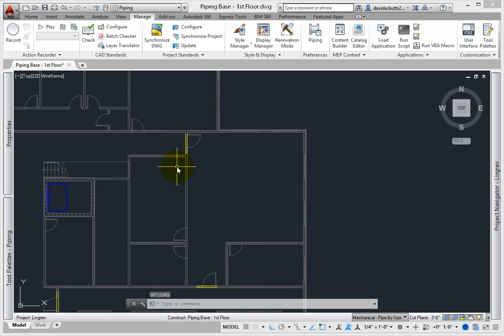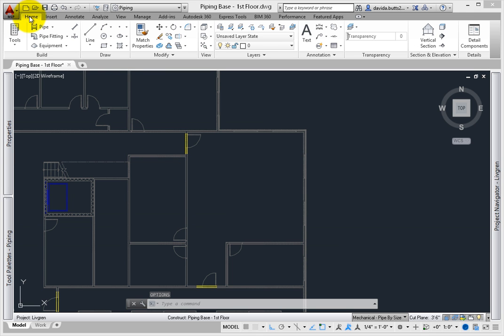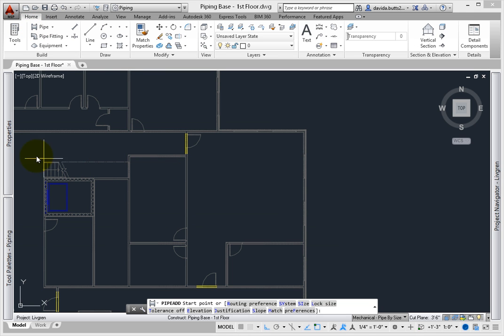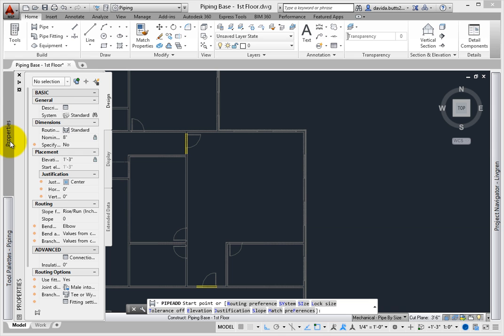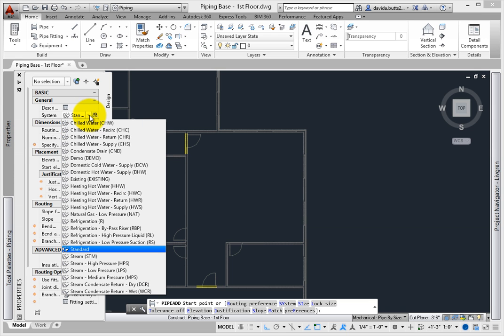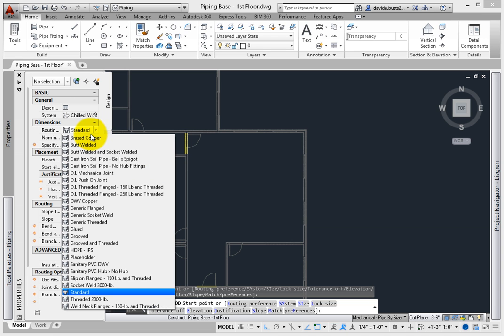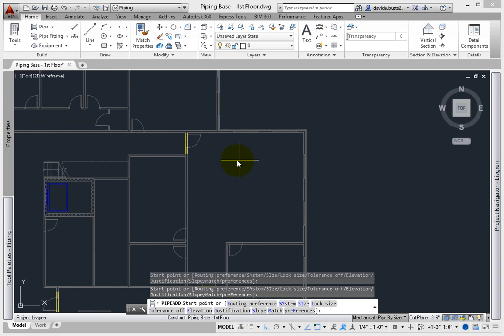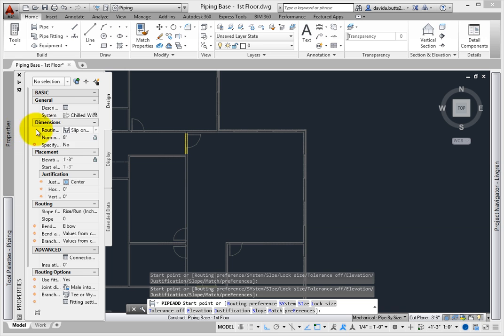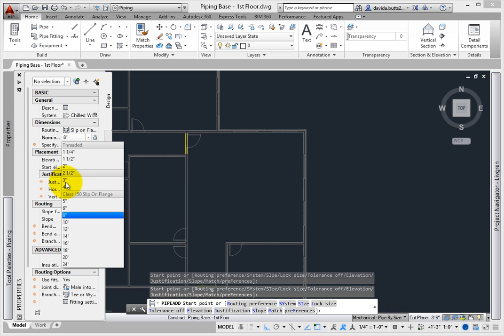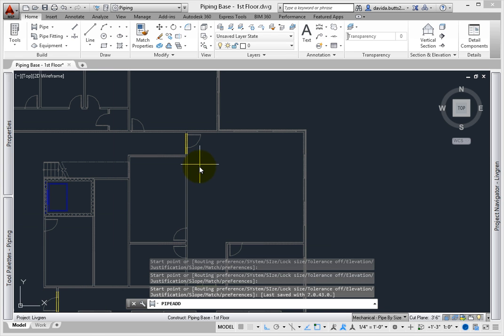Now, try creating an example of the single line graphics. Start the pipe command. From the properties palette, set the system to chilled water, and the pipe routing preference to slip on, flange to 150 pound and threaded. Set the size to 3 inches. In the drawing window, pick a start point and draw a short piece of pipe.